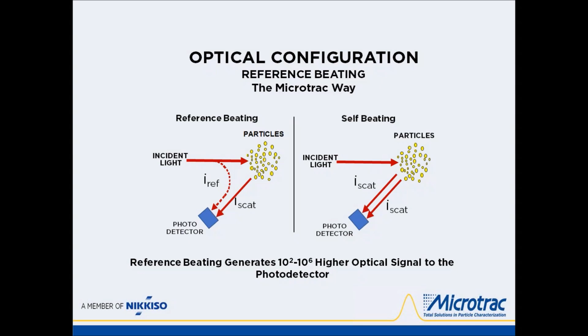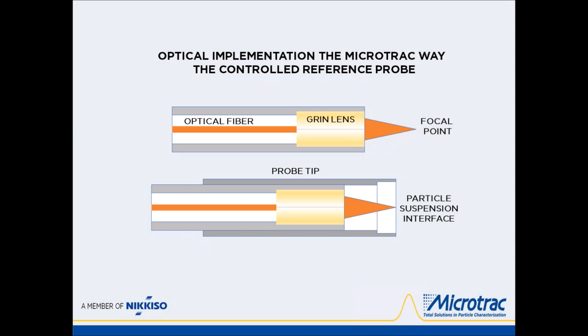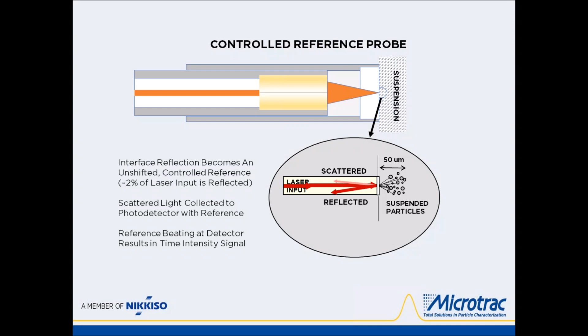The way that Microtrac deals with their probe is basically an optical fiber transmits the laser light into the sample at a specific point. But beyond that, Microtrac decided that it's a good idea to make sure we got a probe tip on the front with a specific window that keeps the focal point just inside the material when it comes for the analysis point. That's better shown in this slide here, where you can see the focal point of the laser is just inside into the suspension around 50 microns. And here is a graphic where you can see that some of that reflected light, around 2%, is what we use as our reference signal. The easiest way to describe it is when you look out a window, you can still see your reflection in the window, but you can also see what's outside. That reflection is what we're using as our reference signal.